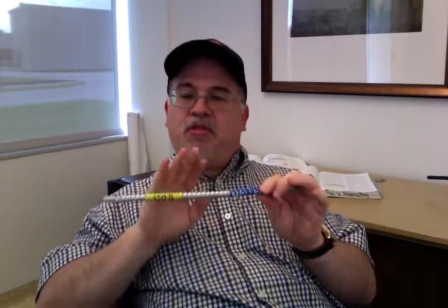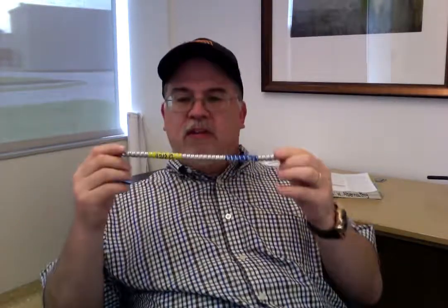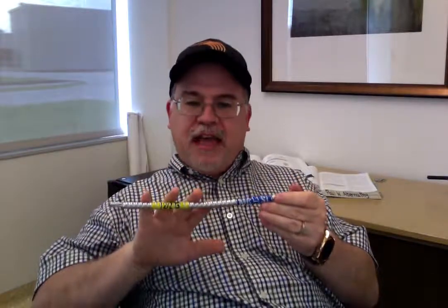Again, that is the location. Having this cable subject to some mild degree of moisture due to construction or due to a freak incident is different, as long as it's not submerged, and as long as the water doesn't get into the ends of it or any contaminated flood water gets into it. That changes the game. So it's really important to know what kind of exposure this cable has been faced with. Then we can give you some guidance after that. But this is a dry location product, wet and damp location product, dry location fitting, wet and damp location fitting. And it's just that simple.